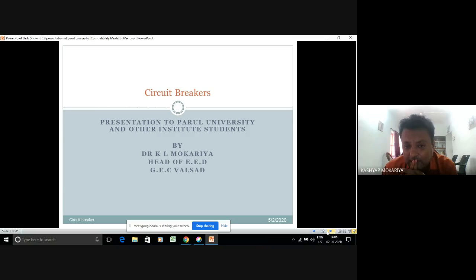So for that, first the operation department in an industry will de-energize the 6.6 kV breaker. Then at the back side, the cable will get discharged, because you have to discharge it by means of a rod. Otherwise, the people working at that part will get affected by shock. And third, they have to tag a red tag saying that this device is ready for preventive maintenance.